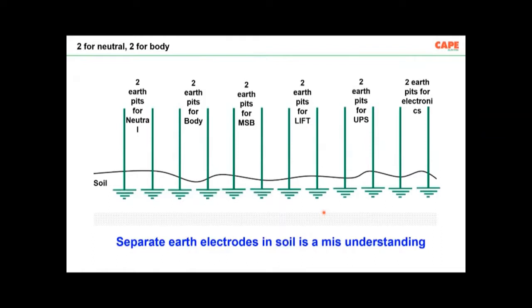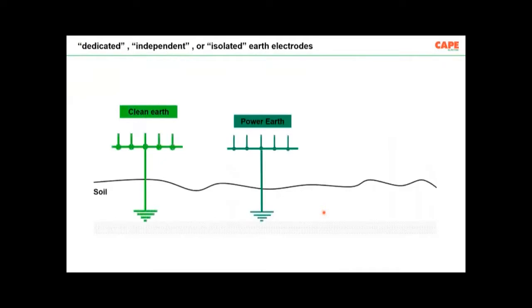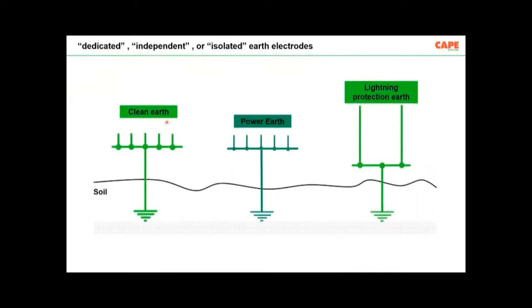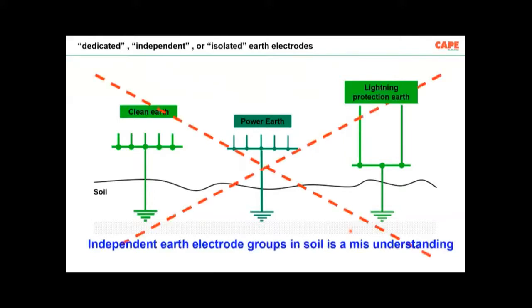This kind of earthing, if you make, you can never achieve safety. So this is absolutely wrong. Nowadays, we also make earthing in this fashion. You know, a group of earthing interconnected, like electronics interconnected together to one earth pit, power earth, all the electrical items to one earth electrode, lightning protection to one earth electrode. Unfortunately, this is also wrong. This is, you should not follow. You will not be able to get the safety in this case.